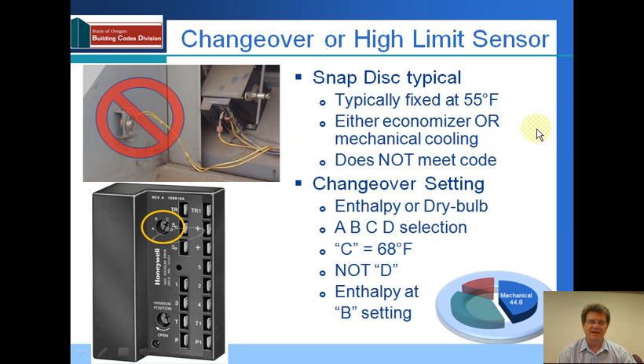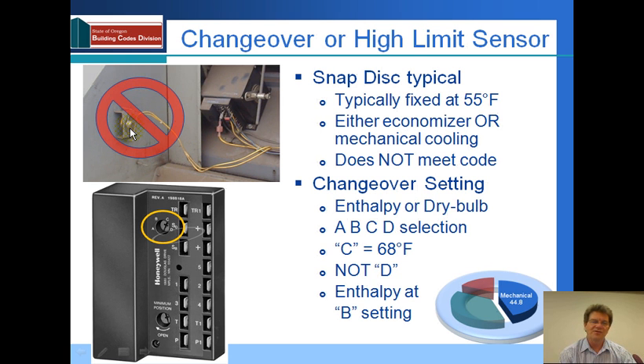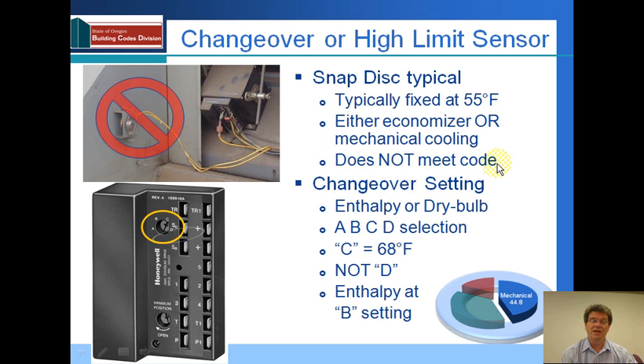One thing that indicates that you do not have integrated economizer control is what's called a snap disk. This is usually located under the hood or where the outside air comes into the unit. It's a small, round, silver disk. This typical snap disk operates at a fixed temperature of 55 degrees, and with this type of control, the unit is set up so that either it's the economizer or mechanical cooling, but not both. This does not meet code and it's not compliant. It actually hasn't been compliant for quite some time, although these units continue to be installed because they are a lower-cost item.